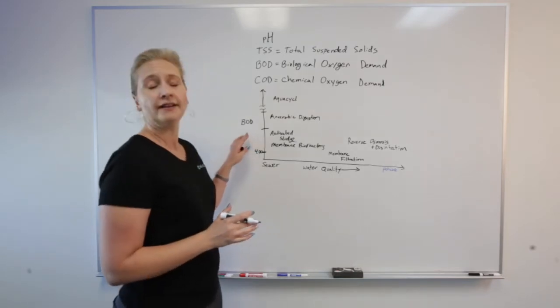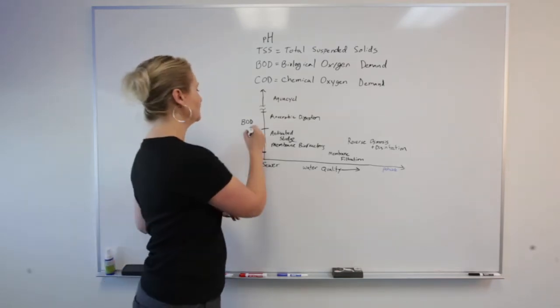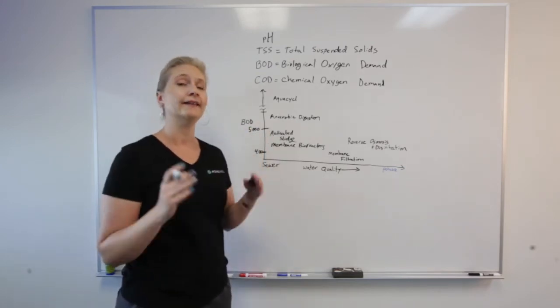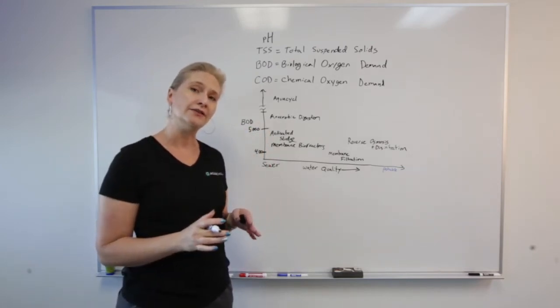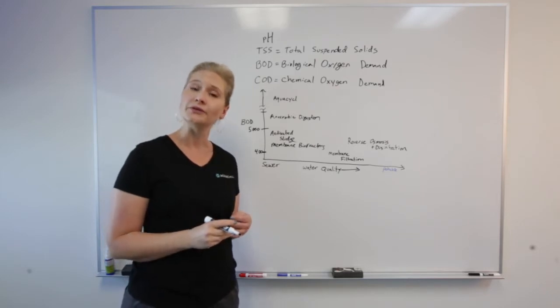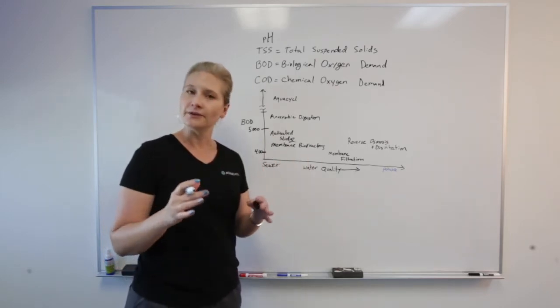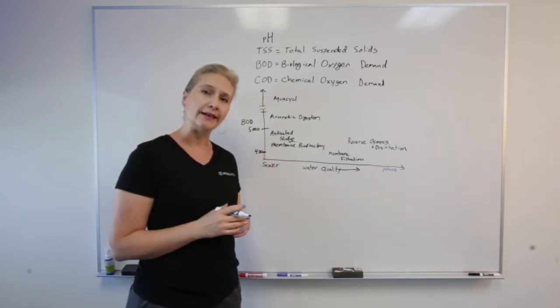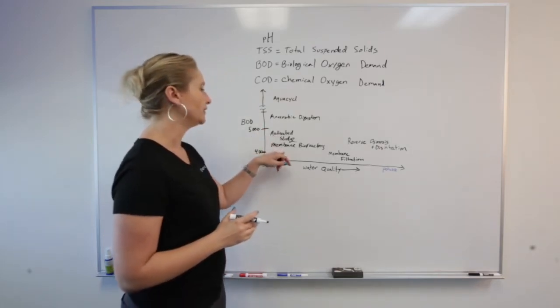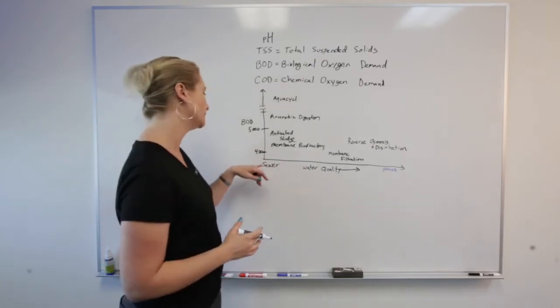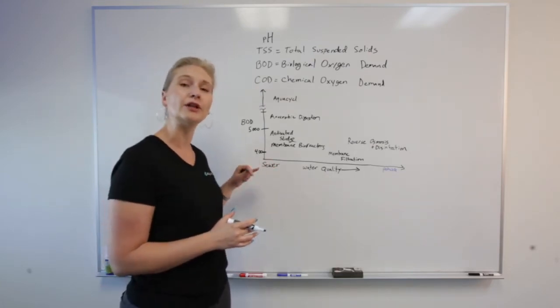But at a higher concentration, like 5,000 parts per million, now that becomes a challenge for the city. So you may have to consider doing some sort of treatment on site. You may have to haul things away. There's a couple different options. But if you want to do treatment on site, you can consider an aeration strategy, especially if you want to get down to a lower BOD level, maybe even lower than 400.